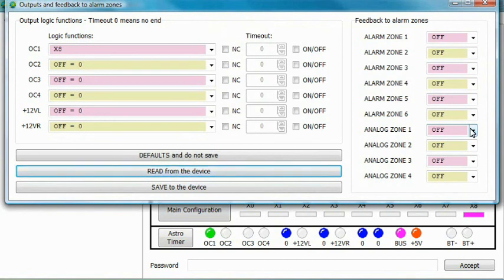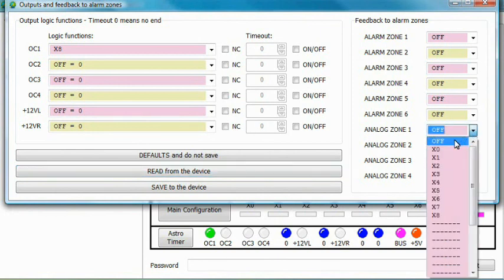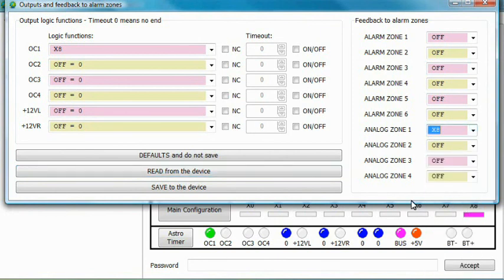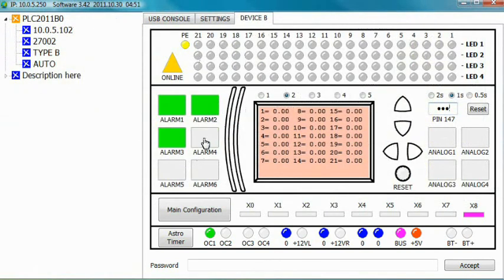You can also try sending feedback to one of the alarm zones. For instance, you can set the analog zone 1 to react to the X8 variable using the feedback option. Remember to save the configuration every time you make a change. Now, whenever the X8 variable appears or disappears, the analog zone will be armed or disarmed. You will also be able to arm and disarm it manually.